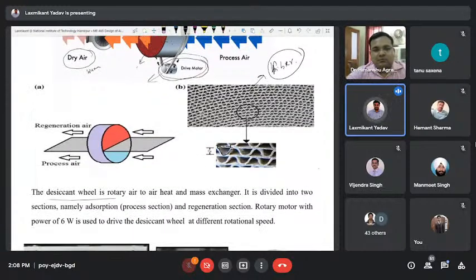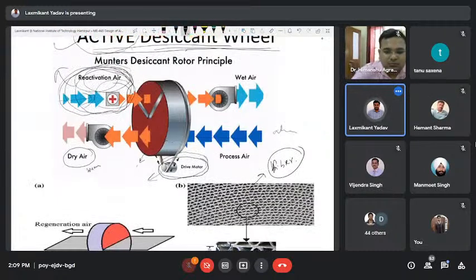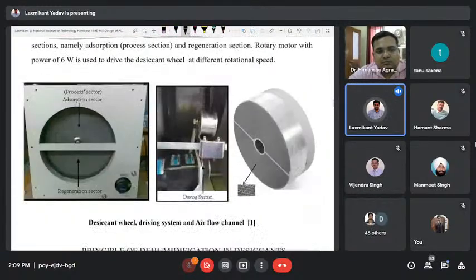The desiccant wheel is a rotary air-to-air heat and mass exchanger, so simultaneous heat and mass transfer takes place. Because heat of adsorption is released, and capillary condensation takes place inside the pores of the desiccant, heat transfer also takes place. In the regeneration section there will be hot air, and the heat of the hot air is transferred to the desiccant. When the desiccant rotates into the process section, this heat comes to the adsorption section. So basically this wheel is a simultaneous heat and mass exchanger wheel.